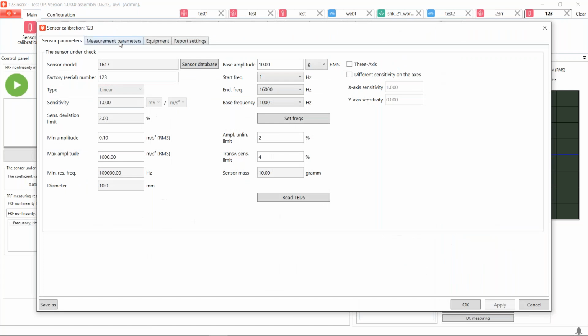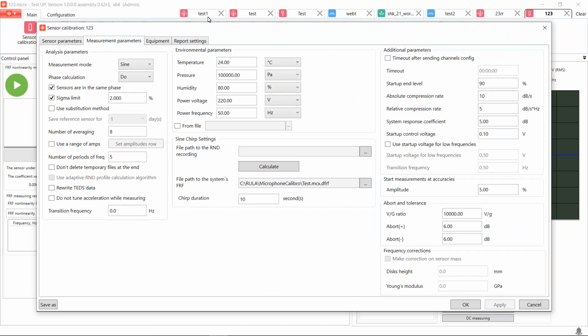Well, in addition to sine wave excitation, we provide calibration with the random signal excitation, and it is presented by FFT H1 and FFT HV measurement modules. In this case, the shaker is excited with a random signal, which contains all the frequencies in the sensor frequency range. And if a random signal is used, sensitivities on all the frequencies are measured simultaneously. This way of calibration reduces the calibration time to 3 or 4 minutes.